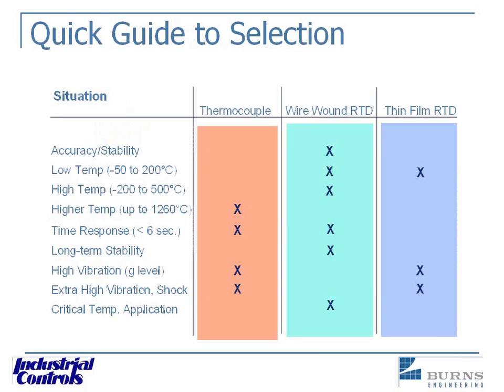And here we have another cheat sheet, if you will. If you can print this off, this is a good one. Again, what it does is it tells you what I can do with a thermocouple, what I can do with wire wound, what I can do with thin film. That's a good one to save. Anything you'd like to add to it, Bill? Well, just there you can see where the thin film, we've got that and a thermocouple for the high vibration shock kinds of things, and where you need the best accuracy, the wire wound is going to be your best choice. Very good.